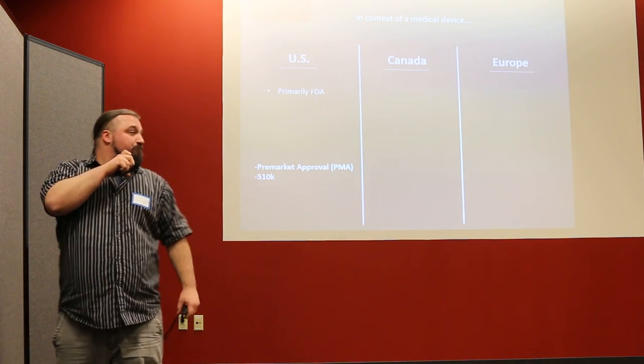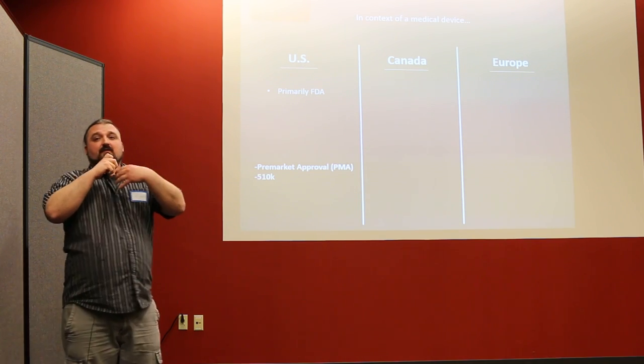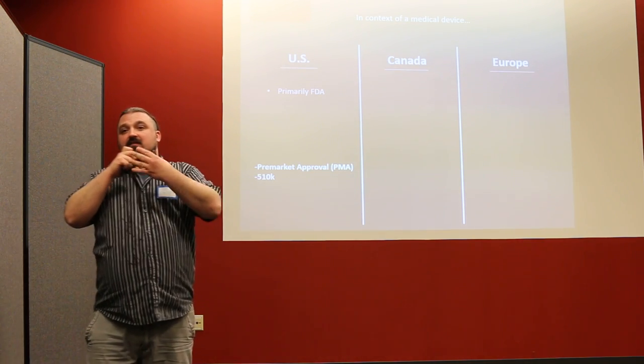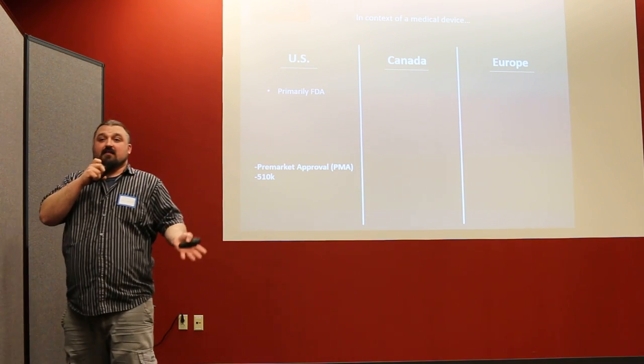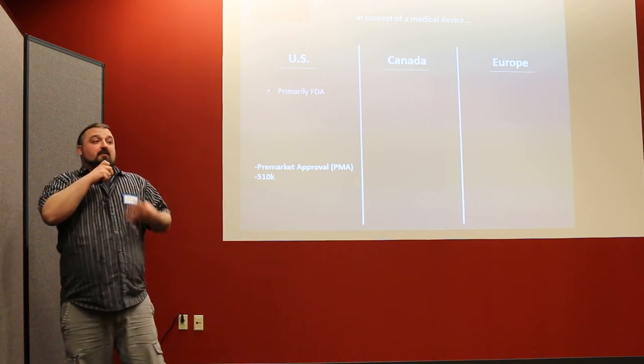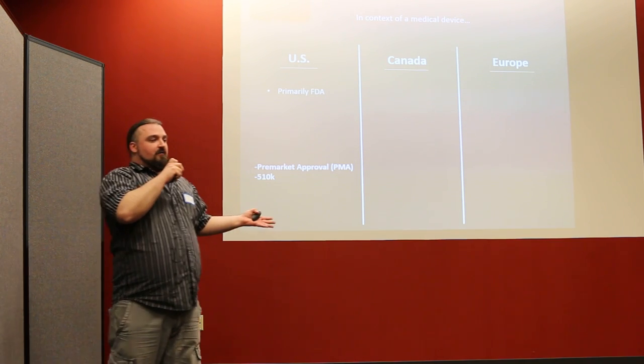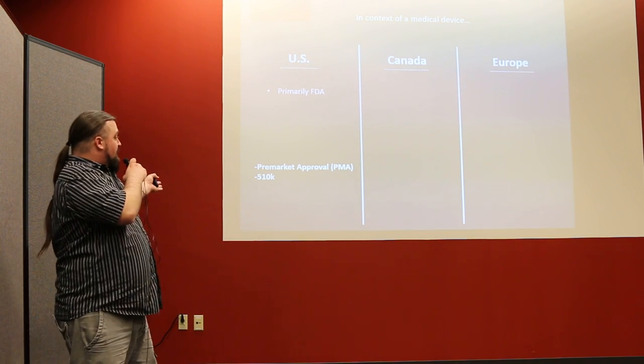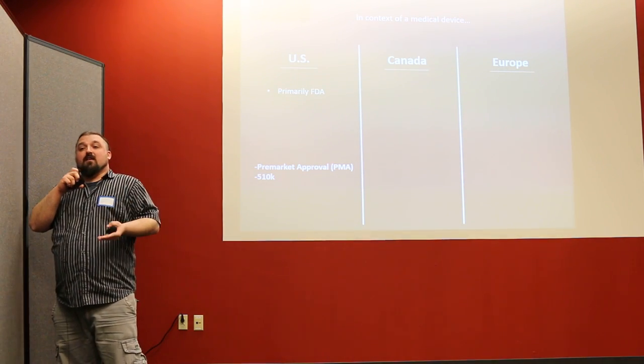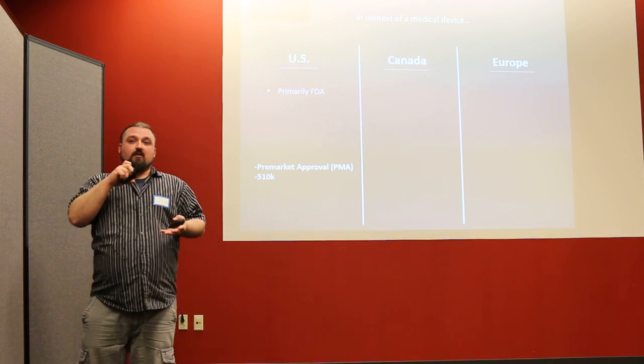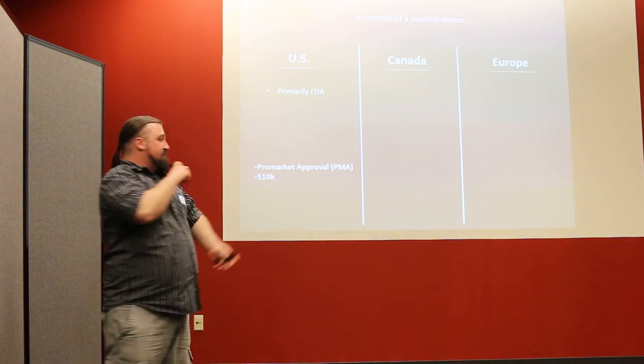A PMA is basically when you have a new idea and want to get it out into the field for the first time — you present all the evidence and data, submit it to the FDA, they review it, and say your product is safe for use. A 510K is slightly different: you compare yourself to an existing technology and prove that you're no worse than that product — essentially that you're equivalent.